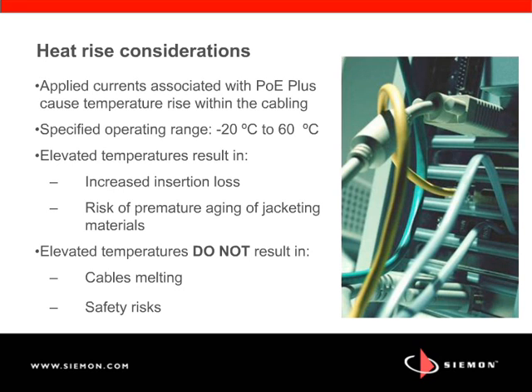So you're at the top of the operating range and you have a little additional heat that's caused by the remote powering application. These elevated temperatures do not result in cables melting. They do not create safety risks. They result in increased insertion loss and potential for mechanical degradation of the cable. So what type of elevated temperatures are we talking about?